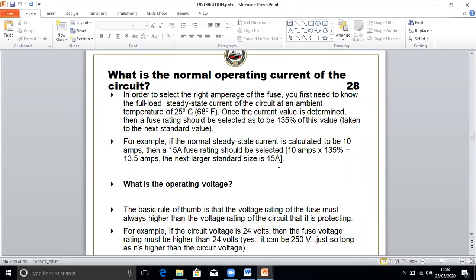In order to select the right ampere rating of the fuses, you first need to know the full steady state current of the circuit at an ambient temperature of 25 degrees. Normally we say it is 25 degrees, and you must know what the steady state current is. Once the current is determined, then the fuse rating is selected as 135%. Hope it is clear. How do you select a fuse? Maybe they can ask you in a viva. Suppose your current is 10 amps, you need to select a fuse. How do you select? You can say steady state current multiplied by 135%. So the next higher value is 15 amps.